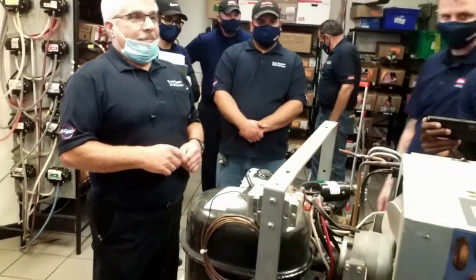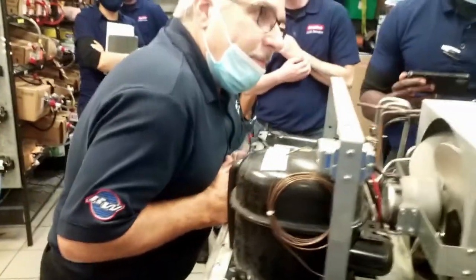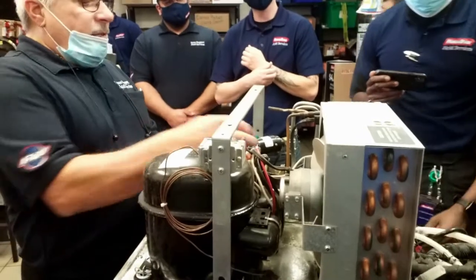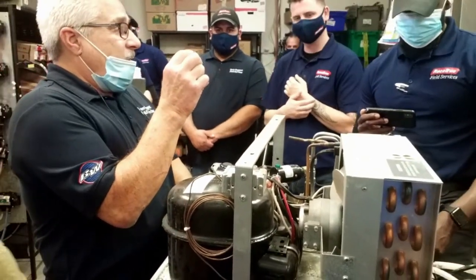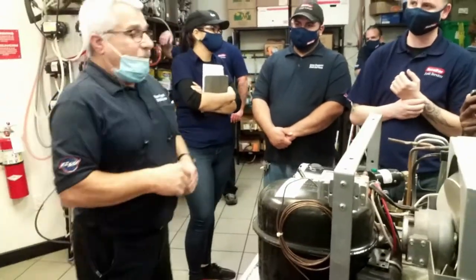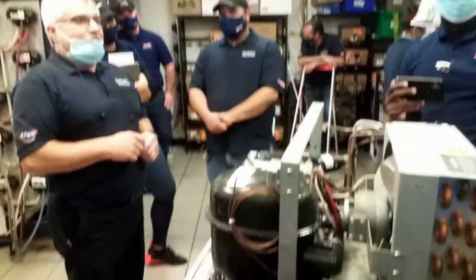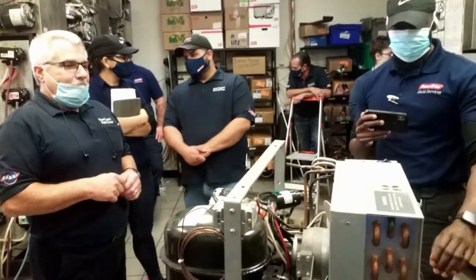And it has a cover on it. I was digging, and I just touched the cover. Yeah, because there's electric in it. It's just a little diaphragm in there against the pressure switch. And when they leak, I've done it. I touched it. Knocked me on my ass. So, like I said, as soon as you have water leaking out, make sure you're going to pull one off.